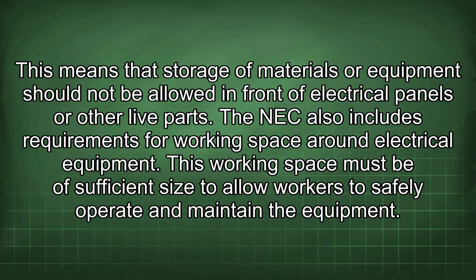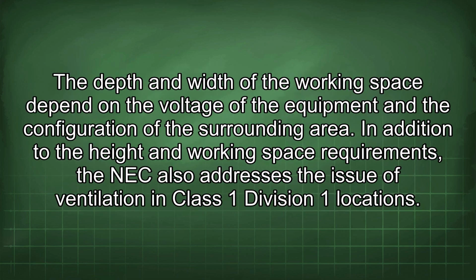This means that storage of materials or equipment should not be allowed in front of electrical panels or other live parts. The NEC also includes requirements for working space around electrical equipment. This working space must be of sufficient size to allow workers to safely operate and maintain the equipment. The depth and width of the working space depend on the voltage of the equipment and the configuration of the surrounding area. In addition to the height and working space requirements, the NEC also addresses the issue of ventilation in Class 1 Division 1 locations.